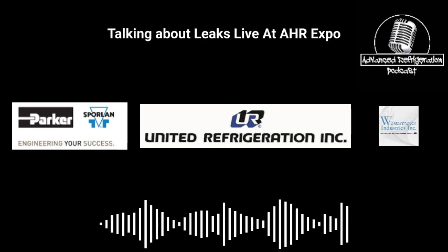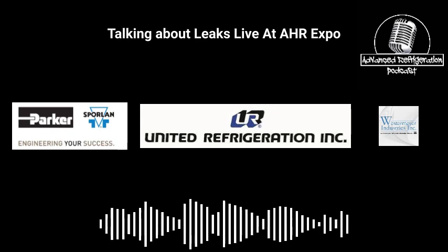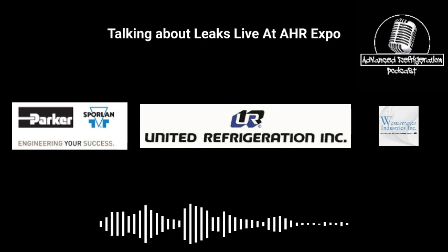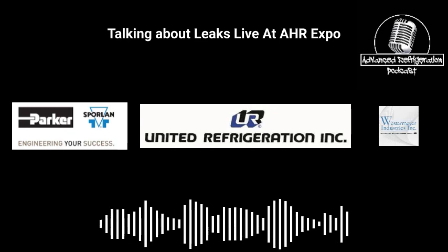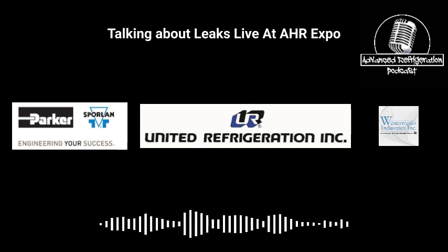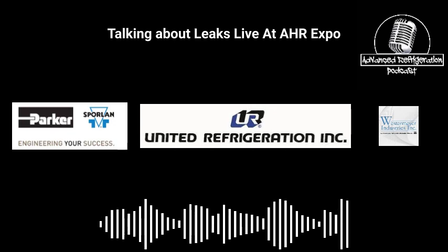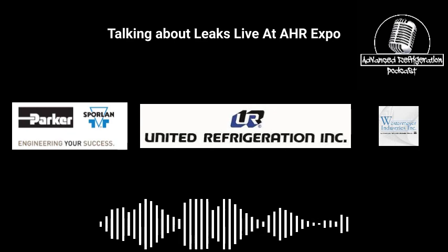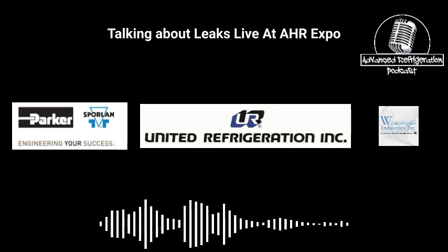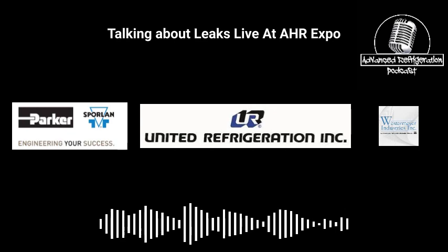But today we're going to talk about CO2 charge management and loss reduction. So, kind of a weird topic, but the way we're going to talk about it is detecting leaks, mitigating charge loss events, and dealing with leaks that are hard to find. So, first and foremost, guys, the majority of the time when you're losing charge in these CO2 racks is when they shut down, whether you have oil failures or power outages. That's when you're getting your refrigerant losses. Unfortunately, those are kind of hard to stop because if you lose power and you don't have a backup generator or a backup unit, you're kind of screwed.